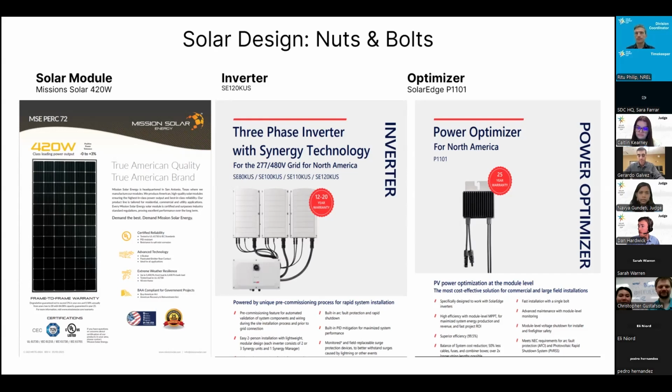Each Solar Edge power optimizer is equipped with a SafeDC feature, which is designed to automatically reduce solar panels' DC voltage to a safe voltage level in the event of inverter or grid power shutdown. Each optimizer performs maximum power point tracking of each individual module for max power output. 2 modules are connected in parallel with each optimizer. This mitigates the possible losses from individual modules due to partial shading, manufacturer tolerance ratings, degradation, soiling, and other derates.